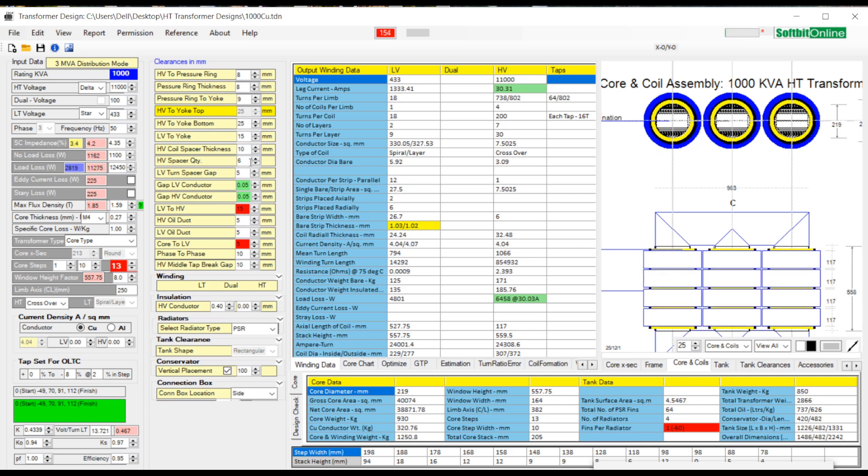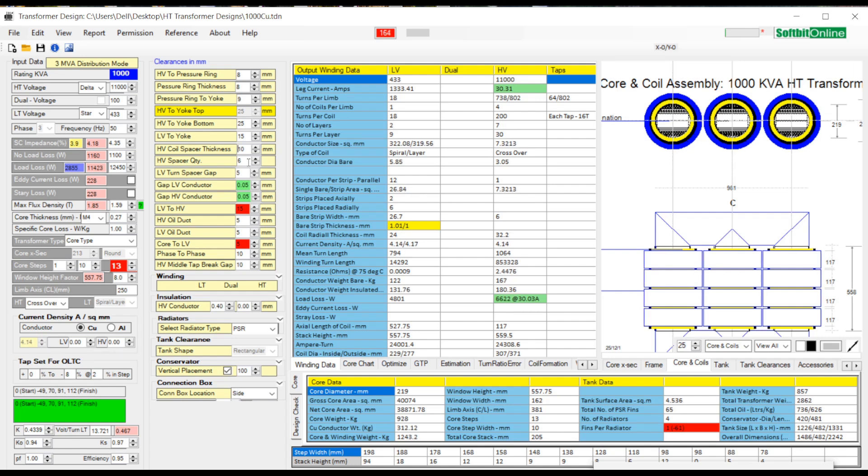Then you need to enter the quantity of spacer blocks below each coil. This affects the axial force on windings.